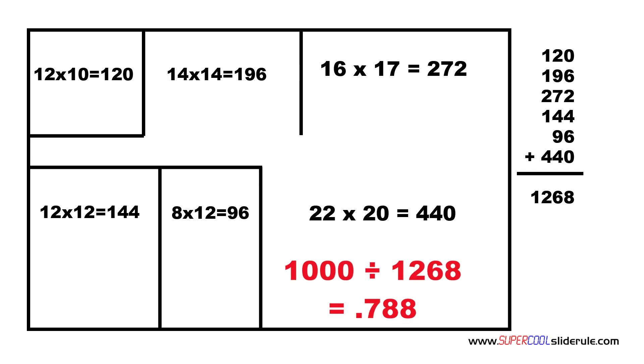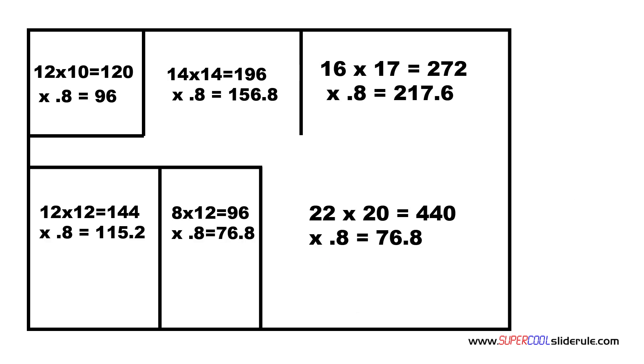We divide this by our total square footage. Our answer is .788. We are going to round this number up to .8. Next, we multiply the square footage of each room by .8. This is our required CFM for each room.